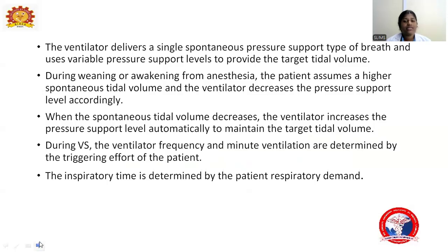So the ventilator delivers a single spontaneous pressure support type and uses variable pressure support levels to provide the target tidal volume. During weaning or awakening from anesthesia, the patient assumes the spontaneous tidal volume and the ventilator decreases the pressure support level accordingly. When the patient's spontaneous tidal volume decreases, the ventilator automatically increases the pressure support level to maintain the target tidal volume. During volume support, the ventilator frequency and minute ventilation are determined by the triggering effort of the patient. The inspiratory time is determined by the patient's respiratory demand.